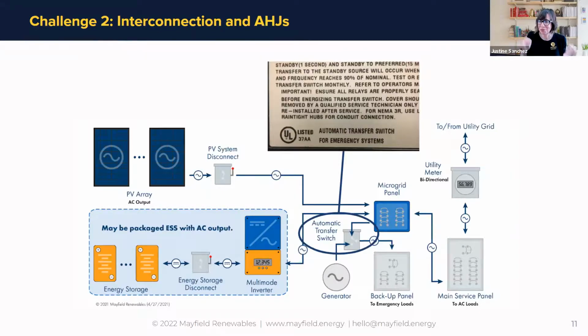When you do this kind of work, way back when, they did selective coordination and testing of the system to make sure things turned on in the order they were supposed to, and nothing got overloaded or tripped things offline. So what we ended up doing is keeping that generator tied to its automatic transfer switch, on the emergency side, the way it always had been. None of that changed. Our generator is the same, the automatic transfer switch is the same, and it's still feeding the emergency side of that transfer switch. So if the grid goes down, or whatever we're normally powering our load panels with ceases to be there, it just flops over and connects to the generator, which directly feeds the emergency loads in the emergency panel. But that meant we had to keep it isolated from our energy storage system, so we couldn't use excess generator runtime to charge batteries, because we had those 2 systems completely isolated.